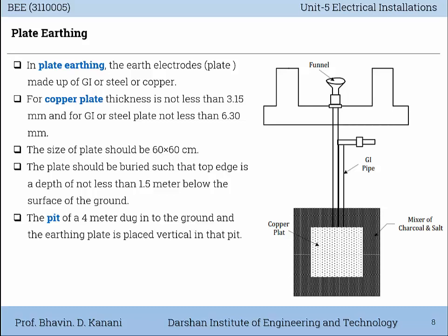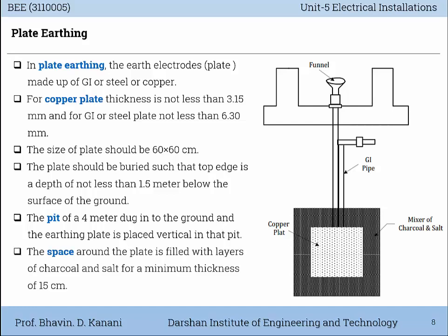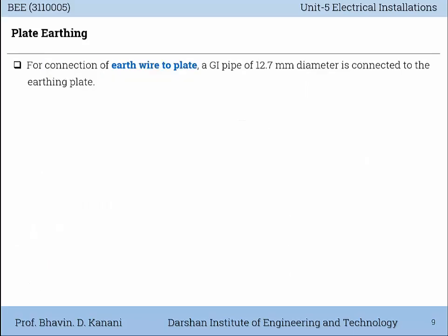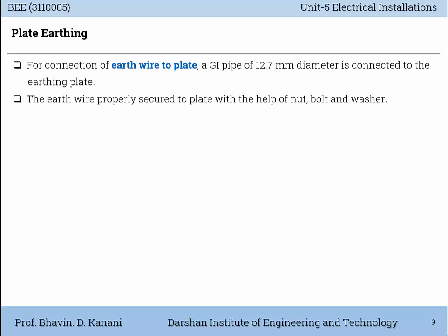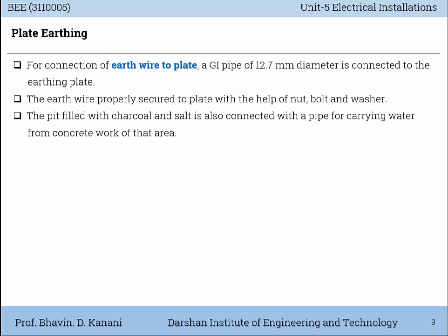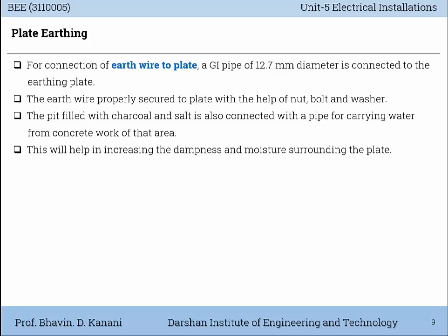A pit of 4 meters is dug into the ground and the earthing plate is placed vertically in that pit. The space around the plate is filled with layers of charcoal and salt for a minimum thickness of 15 cm. For connection of the earth wire to the plate, a GI pipe of 12.7 mm diameter is connected to the earthing plate. The earth wire is properly secured to the plate with the help of nut, bolt and washer. The pit filled with charcoal and salt is also connected with a pipe for carrying water from the concrete work of that area. This will help in increasing the dampness and moisture surrounding the plate.